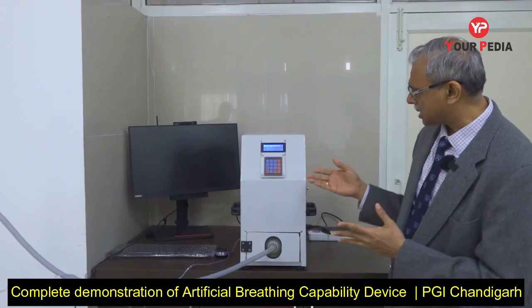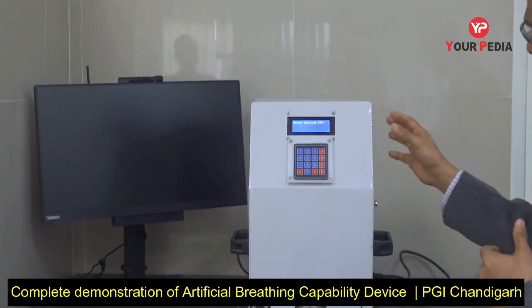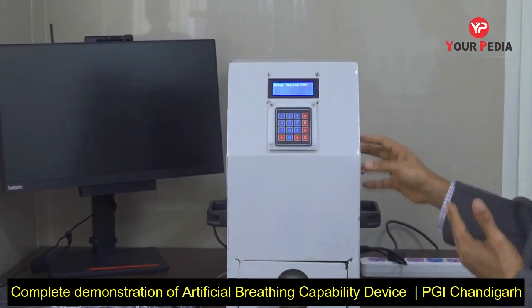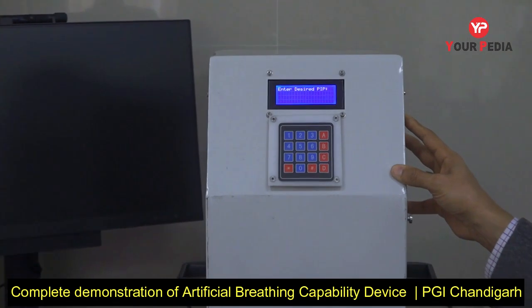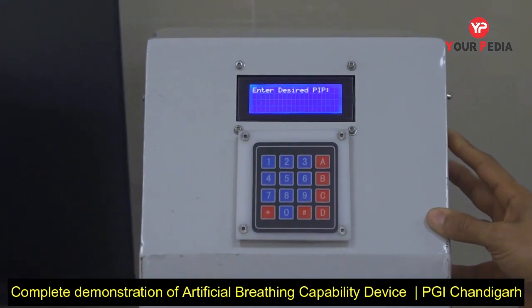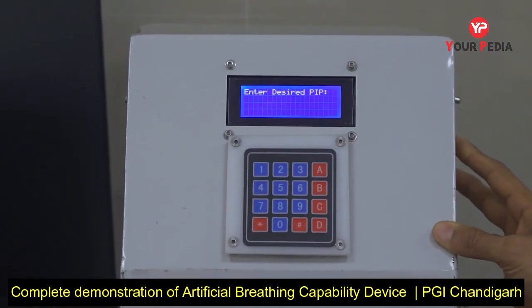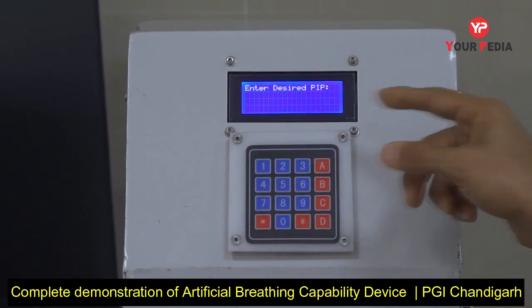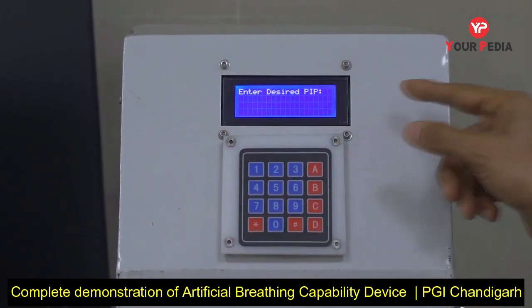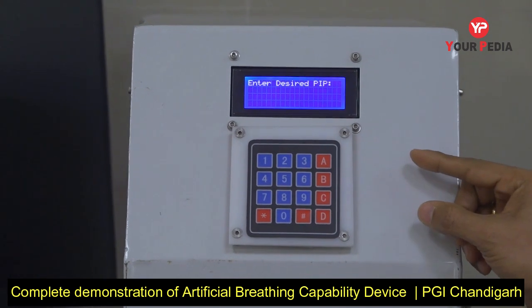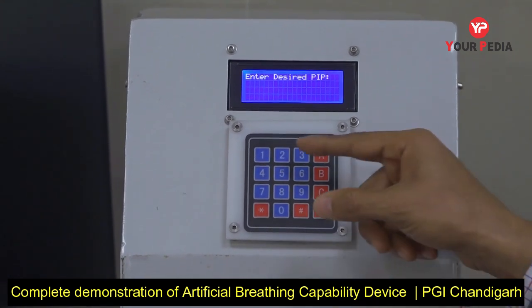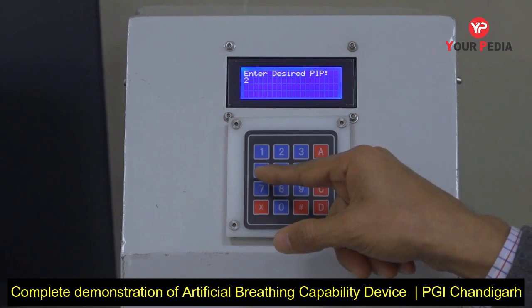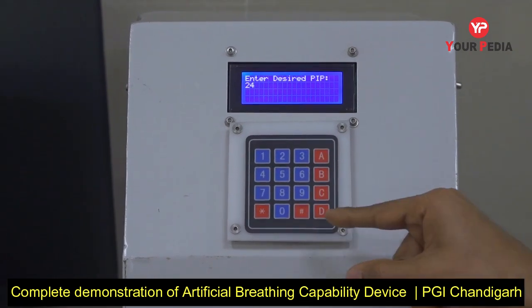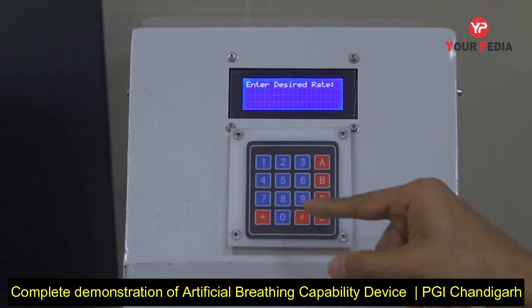Let me now demonstrate how this device actually works. It is really simple to use. When we switch on, the device performs some automated self-checks so that it calibrates itself and then gets ready to use. The first parameter which a user can enter is the PIP, or peak inspiratory pressure, just like a ventilator. So I'm now going to set a pressure of 24. I enter the number 24 and I say yes.